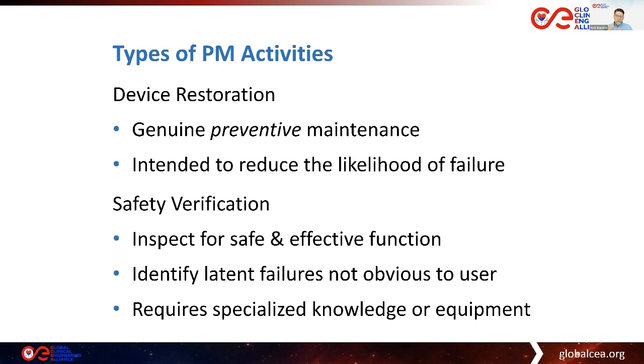And what we do when we do that is we identify latent or hidden failures that are not obvious to the user. So the user is not going to know that the electrosurgical unit output is a little bit low. They normally just, if it's not accomplishing the surgeon's objectives, just turn up the dial a little bit. But there could be an underlying or hidden failure that is important to find out and take care of so that it doesn't cause a problem later. And typically, this safety verification, if it's not something the user can do, requires the specialized knowledge of our technicians, our technologists, or excuse me, requires special test equipment. So these are the two aspects of PM that I think it's important to keep in mind as we design our PM programs.